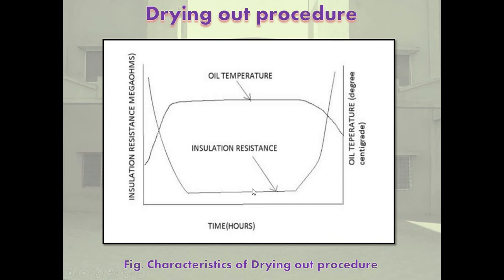Now, the drying out procedure. In the drying out procedure, different types of equipment can be dried by applying heat by any of the following methods: first, circulating hot oil for oil filled equipment, circulating hot air for air or SF6 gas filled equipment, heating by induction coil, heating by short circuit method, etc. In case of a power transformer, the most convenient method is circulation of hot oil through the transformer tank by means of a streamline filter. The drying out is improved and accelerated by application of vacuum to the transformer tank.